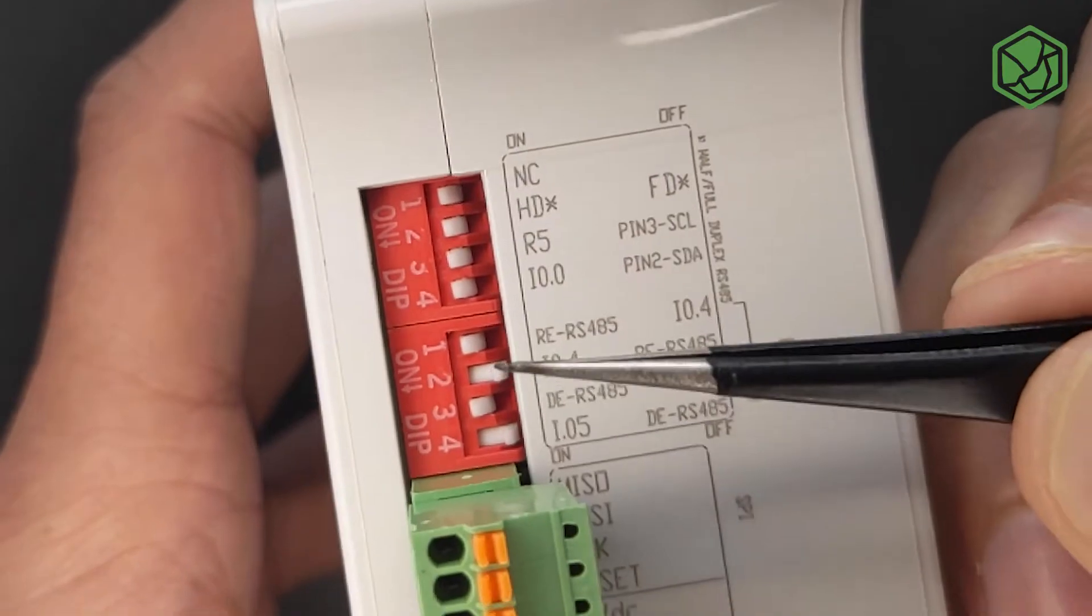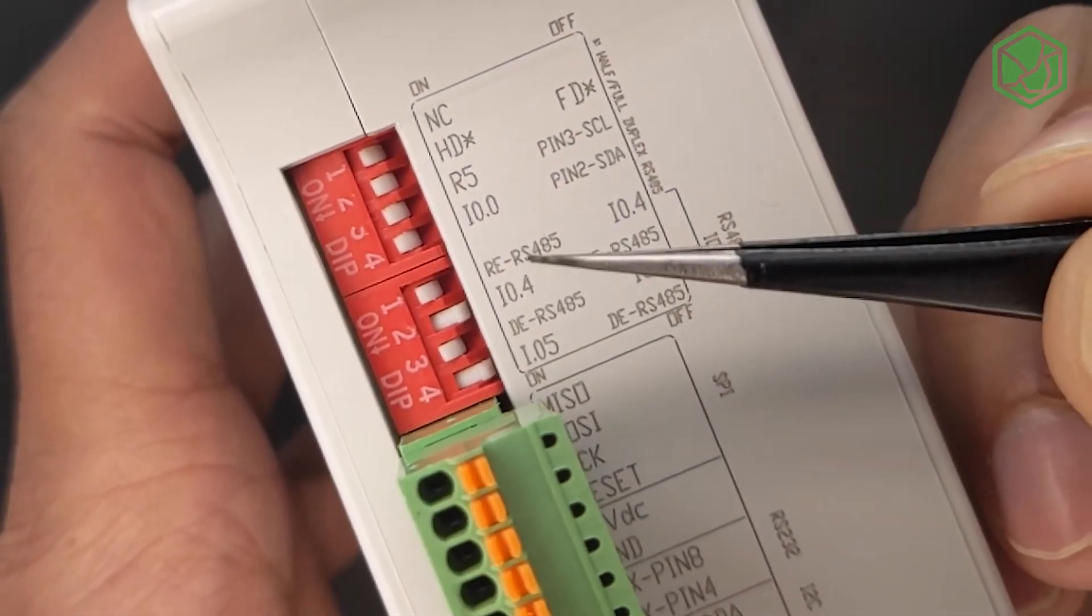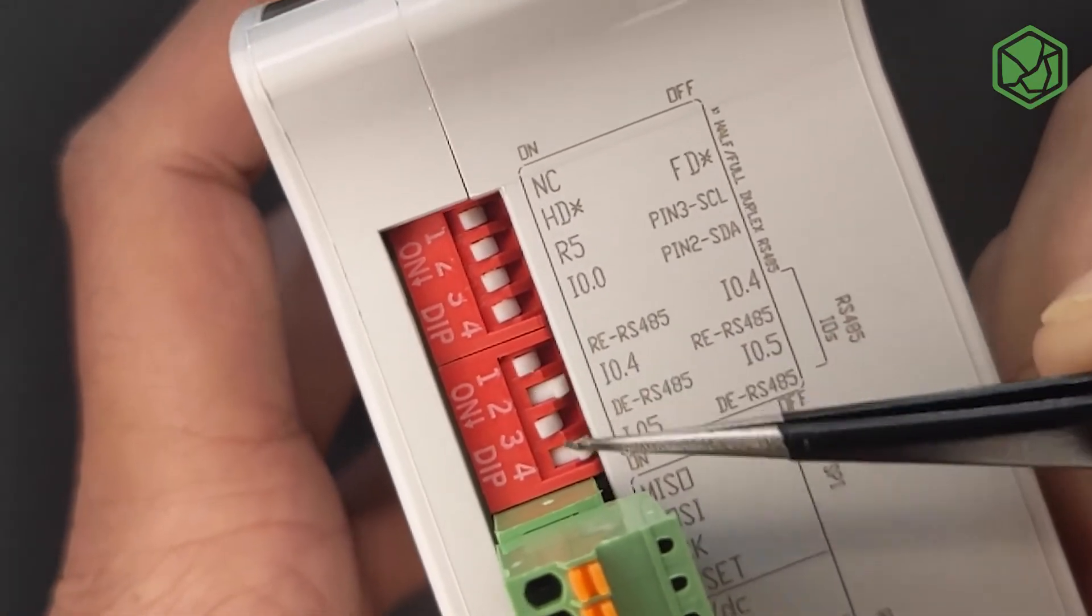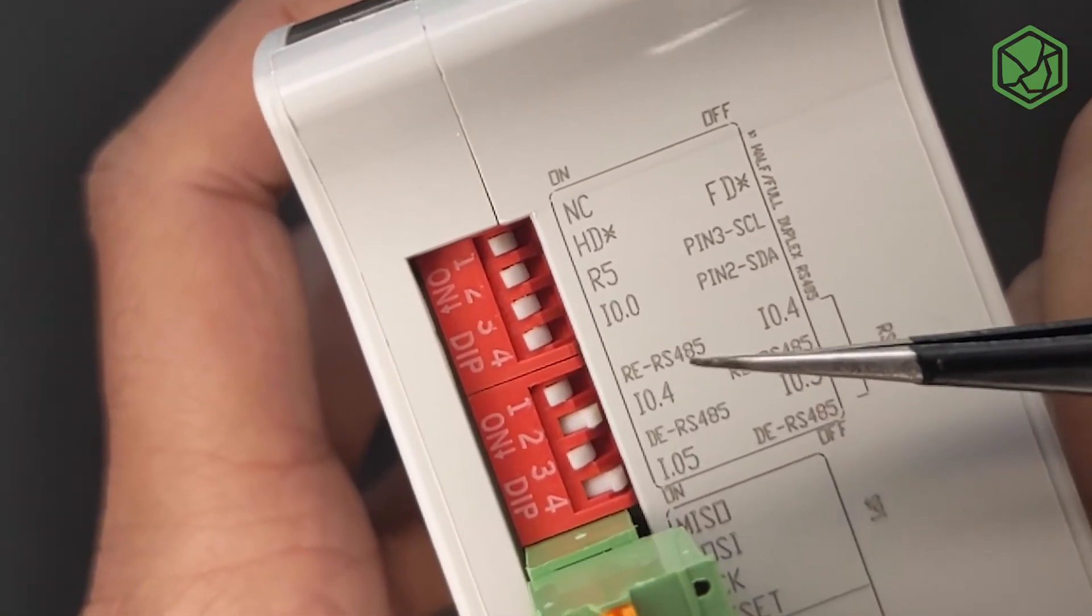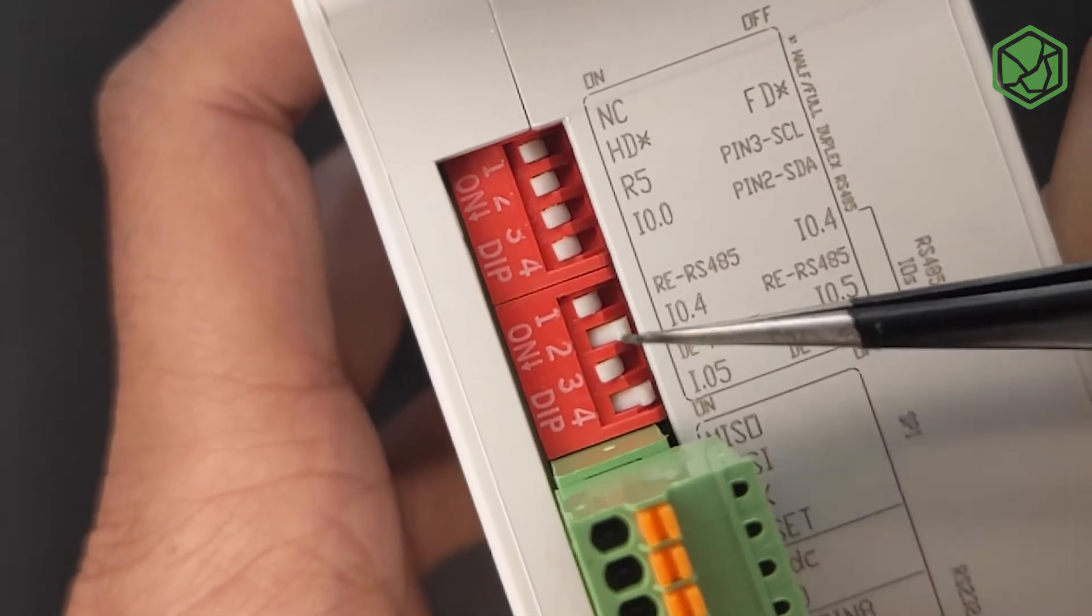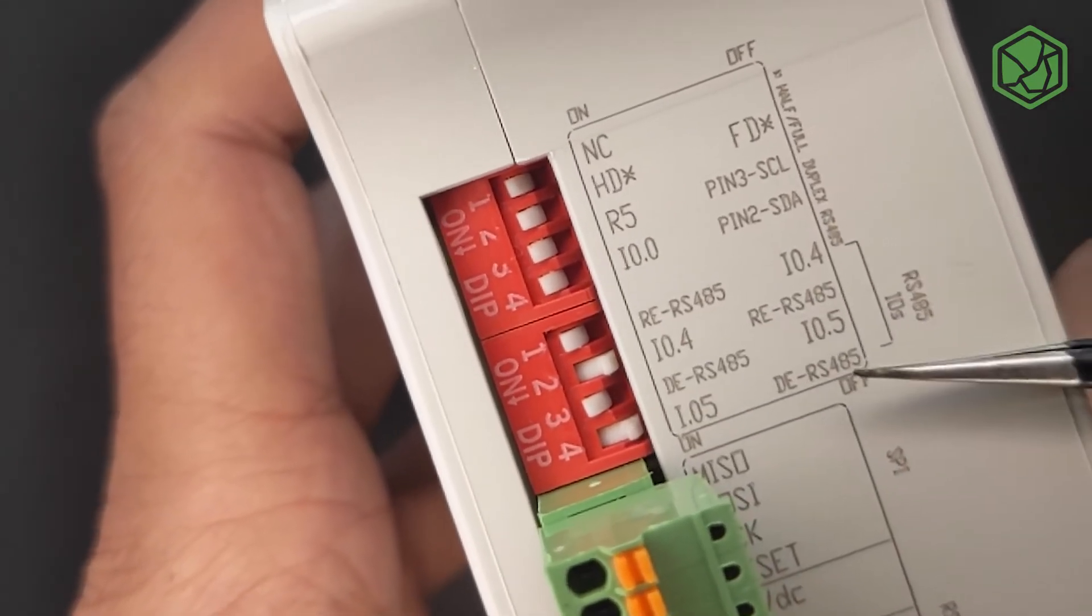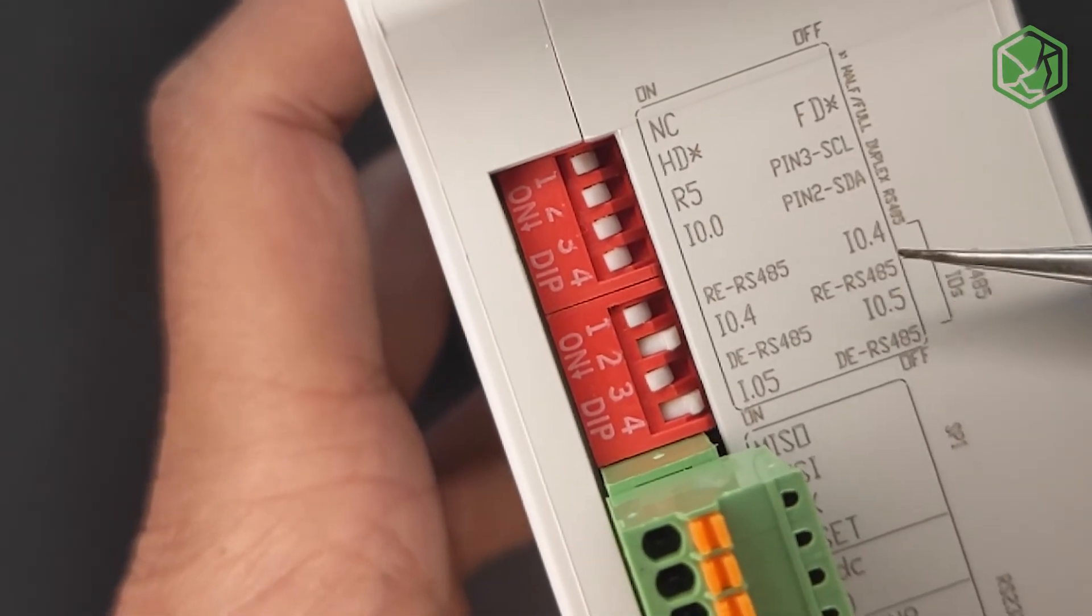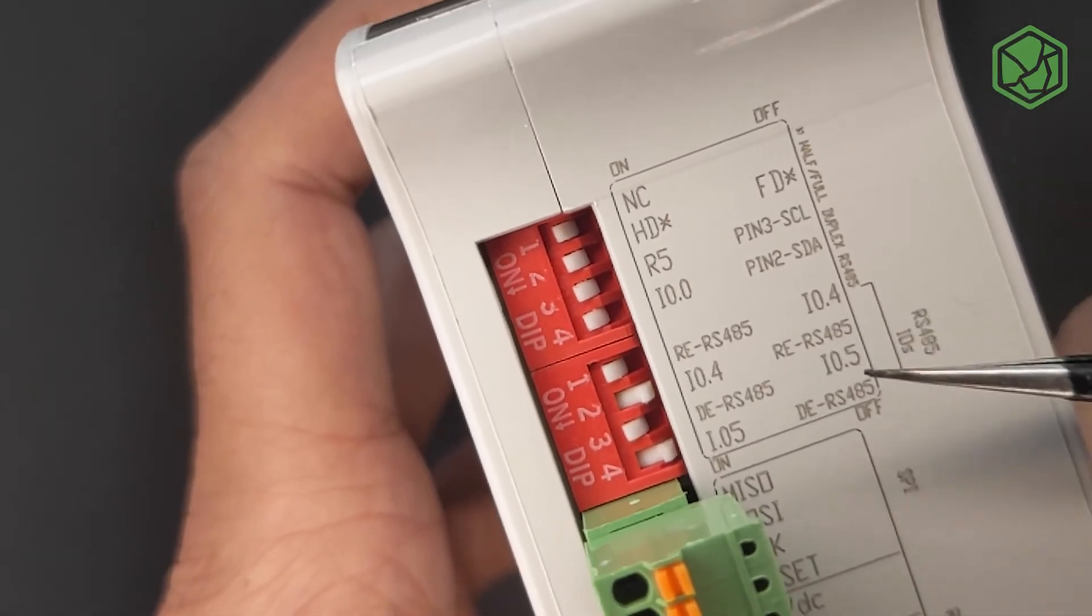Moving on to the second block, you have pin number one and three for receiver enable and data enable of RS-485. They need to be turned on if you've chosen RS-485 communication. And pin number two and four needs to be turned off for RS-485. If they're the opposite, then you have input 0.4 and 0.5 enabled.